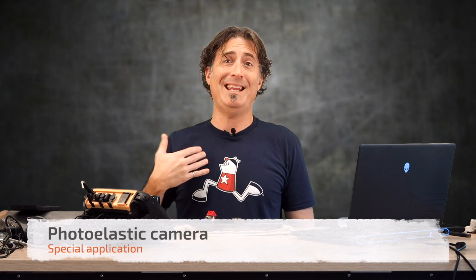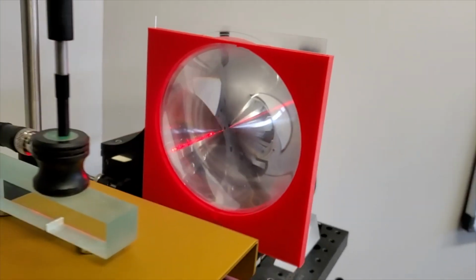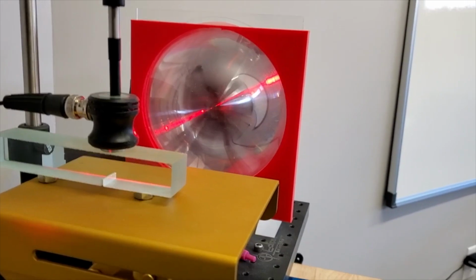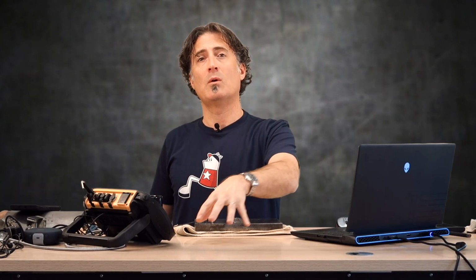There are special applications where I need to use a square wave pulsar, and one of them is the photoelastic camera. Here I've set up a 5 megahertz half-inch transducer, and side by side with the voltage on both the spike and square set at 250 volts, you can see just how much more oomph you get with the square wave pulsar. In order to make a nice image on that, I have to use square wave. But for most of all the other work I do, I don't really care. For most of what we do in the field with UT, whether that's thickness testing or weld testing, spike or square will work just fine.